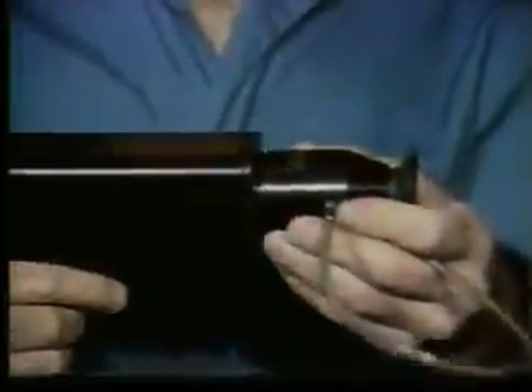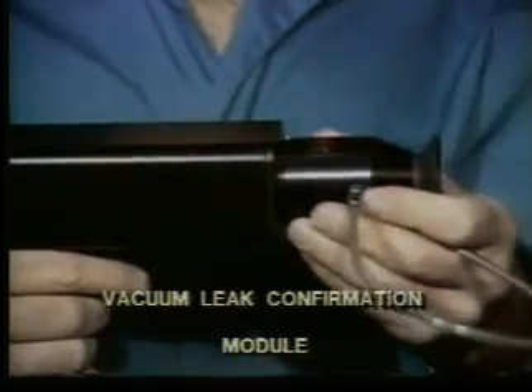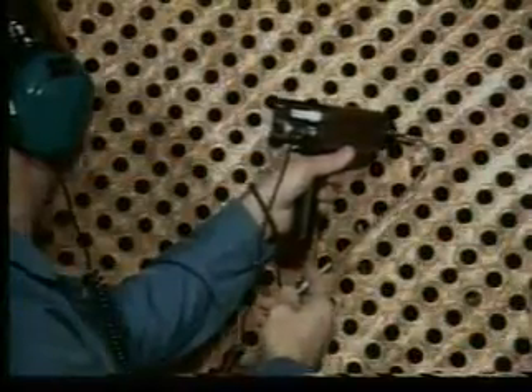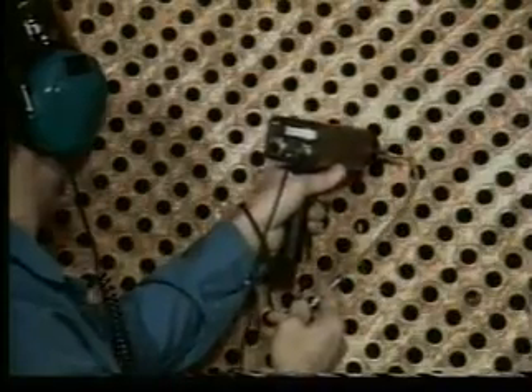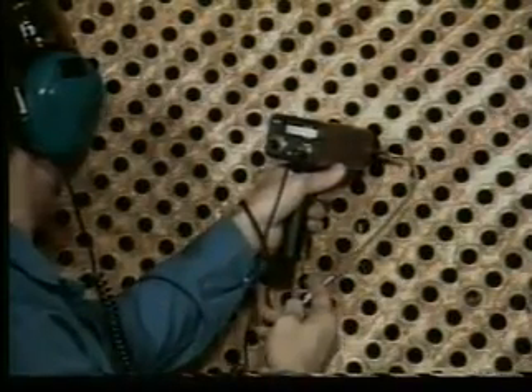Next, we will discuss how to handle the problem of steam impingement. As steam rushes across condenser tubes, it generates a noise with ultrasonic components similar to those of a leak. This sometimes confusing sound is called steam impingement. To differentiate between steam impingement and air in leakage, use the vacuum leak confirmation module in place of the regular scanning module. Seal off the end of the suspected tube, isolating it from the rest of the tube sheet. Then listen and observe the meter.